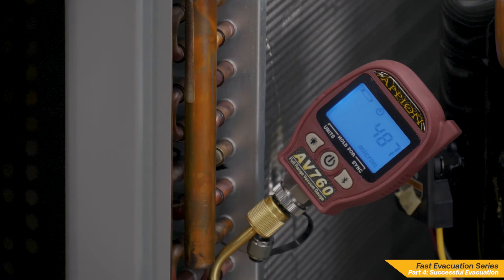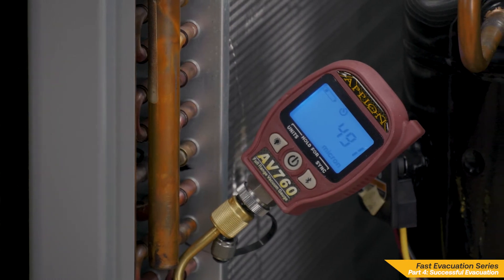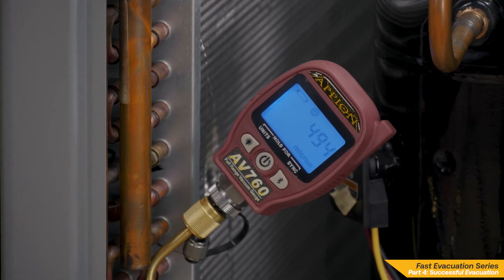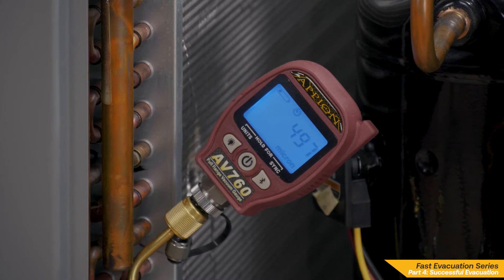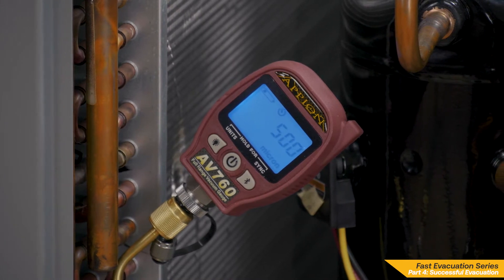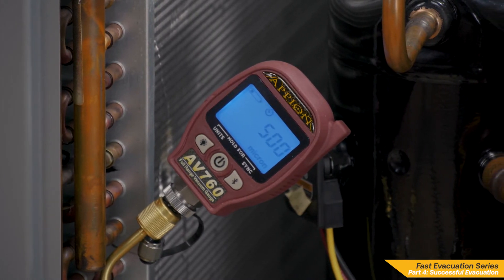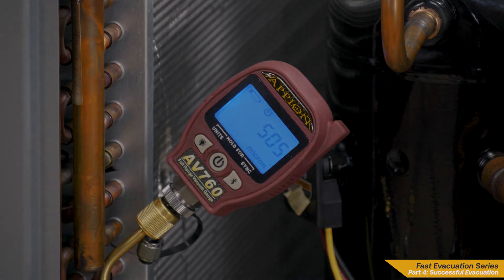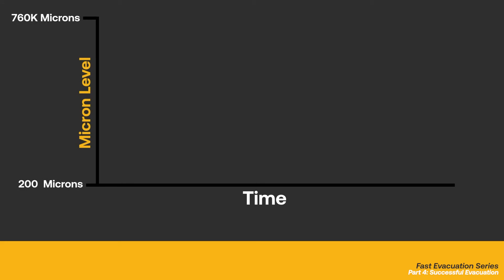However, if the micron level climbs higher than the acceptable rise during the duration of the test, the evacuation is not finished. The micron gauge can still provide answers about the current state of the system. As more time passes with the system still isolated, the micron gauge can indicate several issues: an incomplete degassing or dehydration, contaminants inside the system, or a system leak.